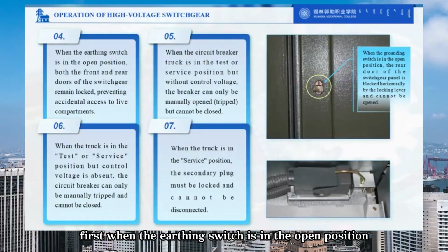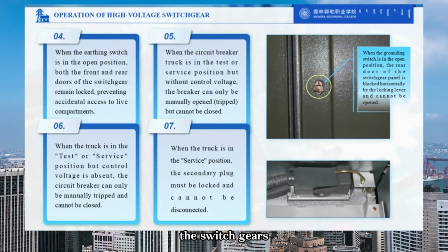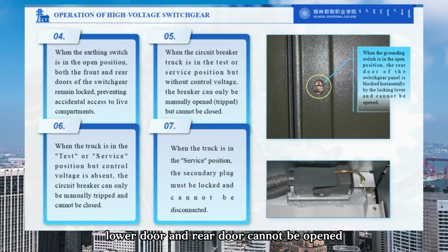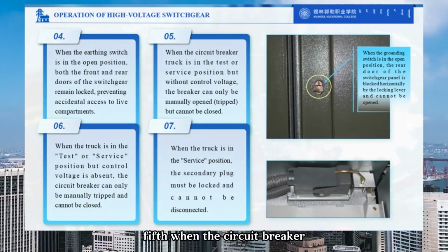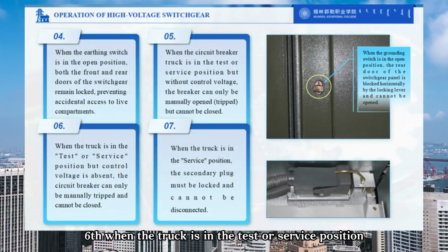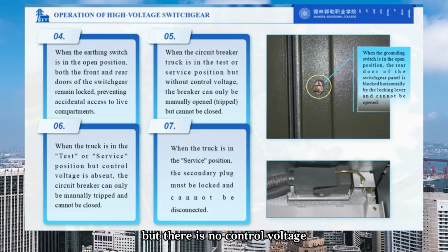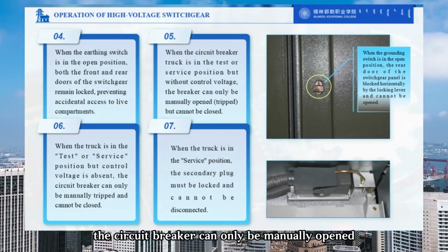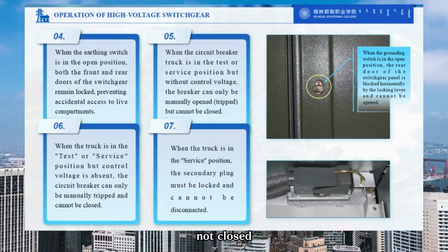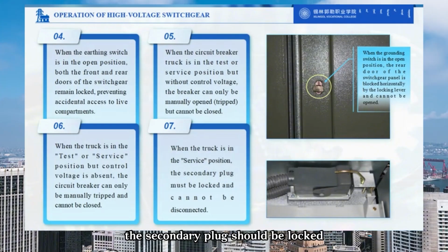Fourth, when the earthing switch is in the open position, the switchgear's lower door and rear door cannot be opened, preventing accidental access to live compartments. Fifth, when the circuit breaker truck is in the test or service position, and there is no control voltage, it can only be manually opened, not closed. Sixth, when the truck is in the test or service position, but there is no control voltage, the circuit breaker can only be manually opened, not closed. Seventh, when the truck is in the service position, the secondary plug should be locked and cannot be removed. Now, let's watch a video.